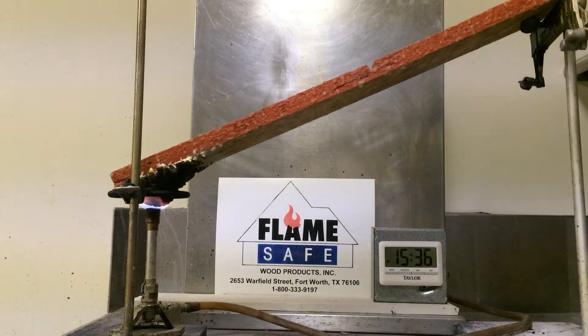FlameSafe's Fire Poly FP100 has the highest intumescent rate of any product on the market. Applied on OSB, it also meets the qualifications for a FRS rating, which means it can be used as air chases. The requirement for an air chase has to do with the smoke development index. FlameSafe's Fire Poly, when applied to OSB and tested according to the ASTM E84, had a smoke index rating of 40, which is substantially less than what the requirement is.